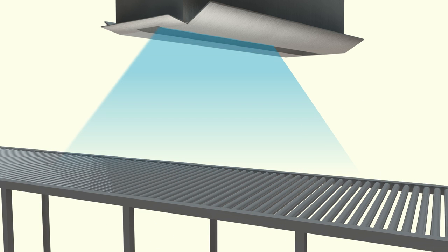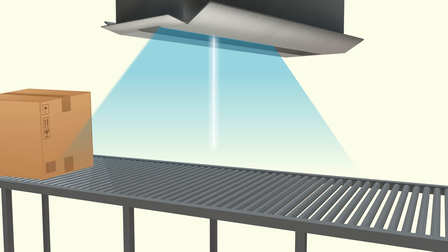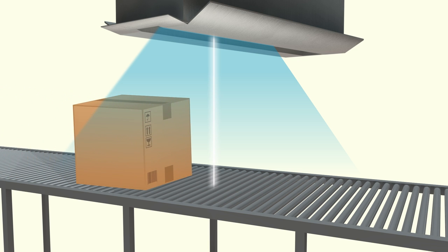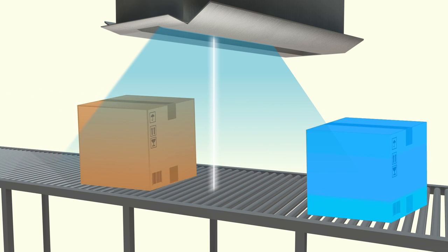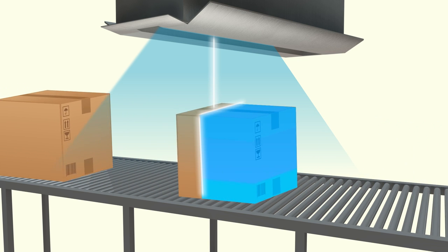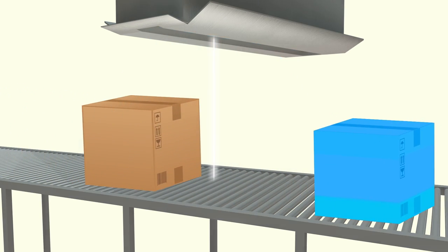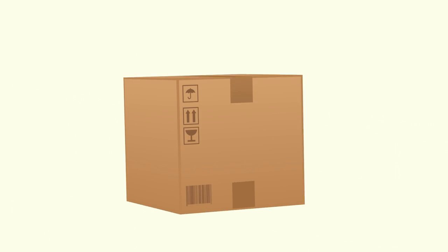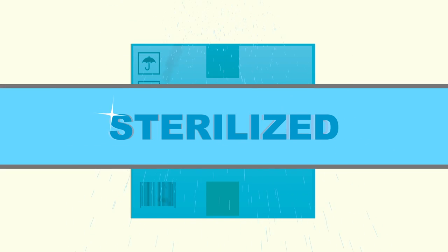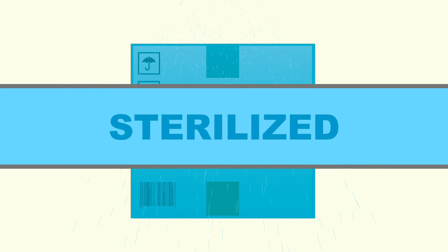Boxes of medical devices are put on a conveyor in a single layer, and as they pass through the beam, the electrons penetrate the cardboard box and all the medical devices in their individual packages inside the carton. Harmful microorganisms are completely inactivated with minimal effect on the medical devices.